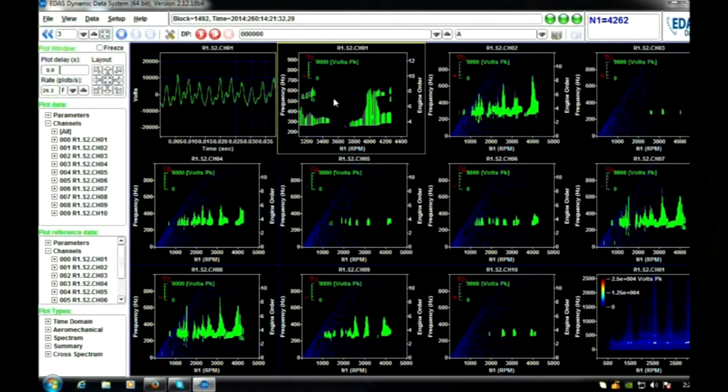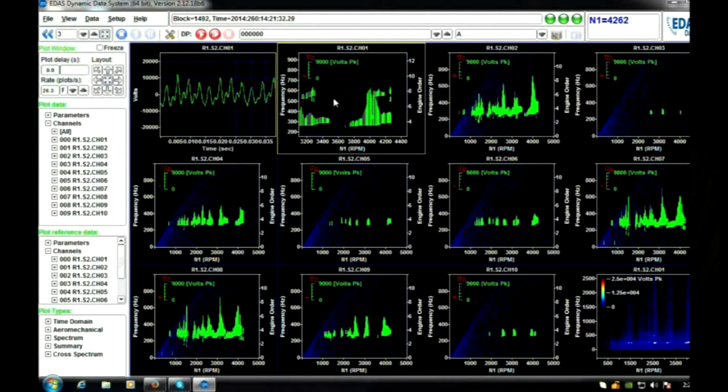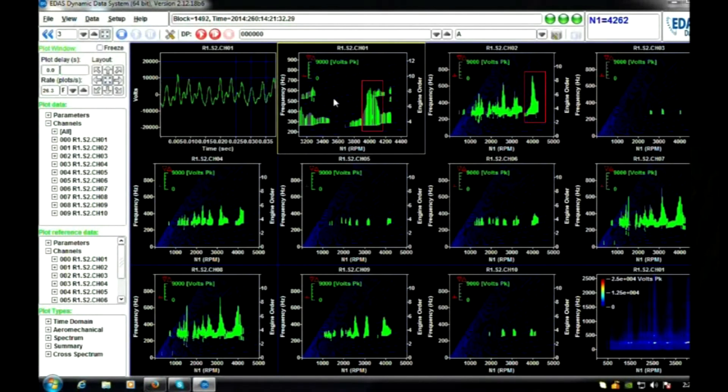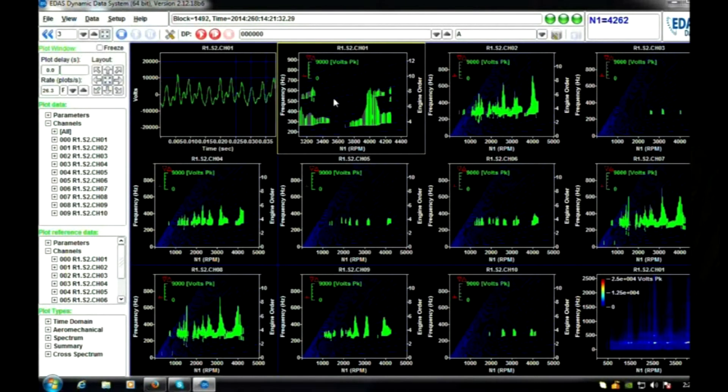Because there is only one magnet, the resonant frequencies of the rotor are excited at various harmonics, causing the blades to resonate at the same frequency over the entire speed range. This is shown by blossoms on the Campbell diagram.